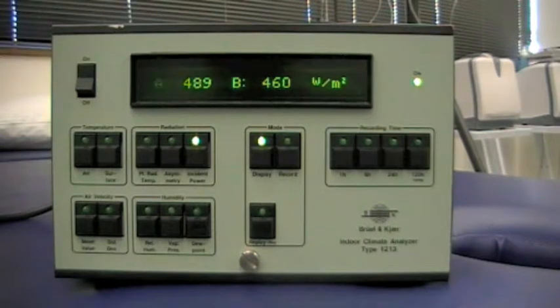This is also looking at the radiant heat and information from the probe, from the two surfaces. Displaying on the left hand side, the A surface which is close to the window, that is the amount of radiant heat being received by that surface, 489 watts per square meter. Whereas on the B surface, there's only 460 watts per square meter. So there's quite a difference there between the two.